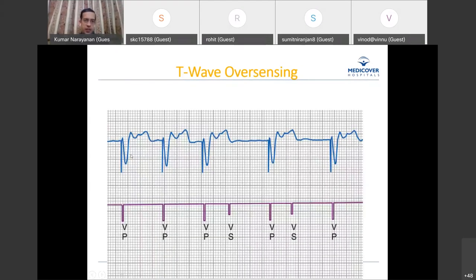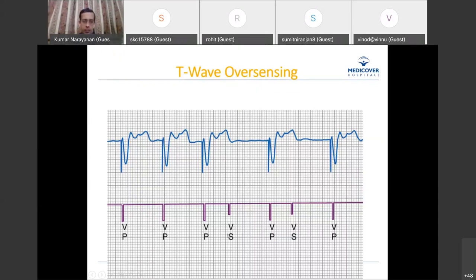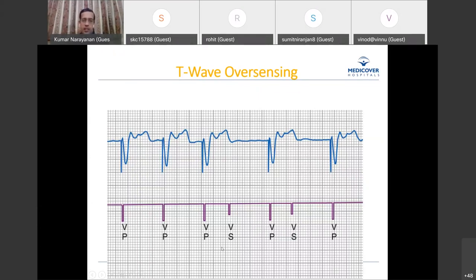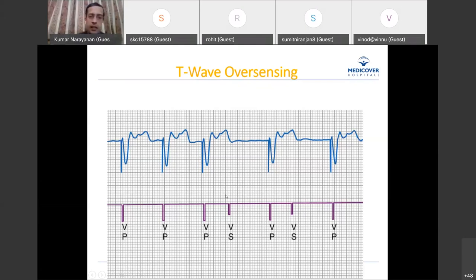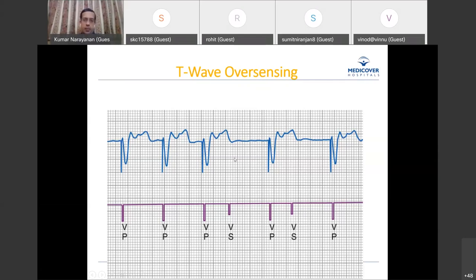An ECG example shows three paced events followed by an unusual loss of pacing. The pacemaker annotation shows Vp, Vp, Vp, then Vs — the pacemaker claims it sensed a ventricular event, so it did not pace. But correlating with the surface ECG, there is no R-wave there — only a prominent T-wave. The pacemaker sensed the T-wave, inappropriately inhibited itself, restarted its timing interval, and only paced again after that interval expired. This is an example of over-sensing.